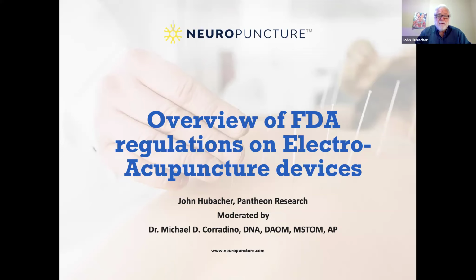So when you have an electroacupuncture device, it has been tested according to standards for electroacupuncture, and it's a very unique category of electromedical equipment. It's quite different from the similar but different category called TENS, transcutaneous electrical nerve stimulation. There are two very different categories of testing because they have different ways of applying the electricity to the body. TENS machines have large surface electrodes, 1 inch square, 2 inch square, that go on the surface of the epidermis. The electroacupuncture machine, of course, has a needle, percutaneous, inserted in the skin with a fine needle point that goes into the tissue. Because of this, they have very different safety standards. So an electroacupuncture device, if it's registered with the FDA, has been tested according to a whole unique set of safety standards that we do have to comply with.